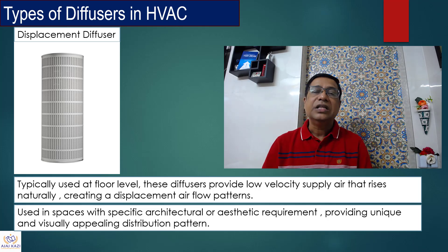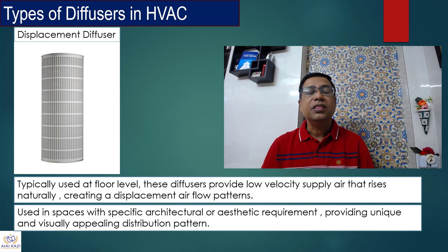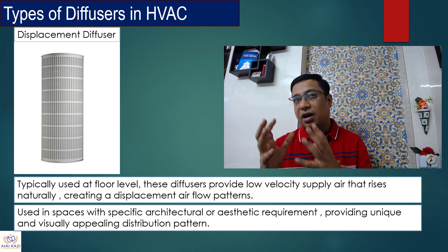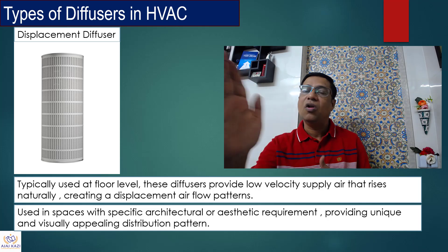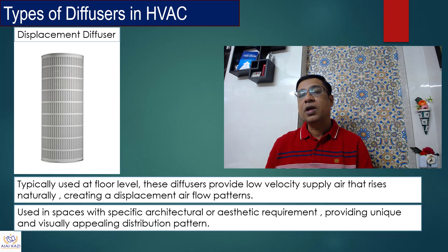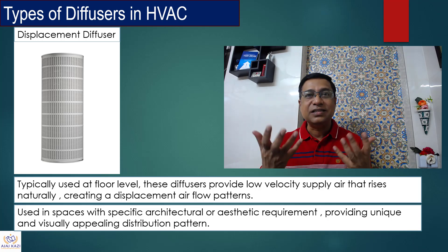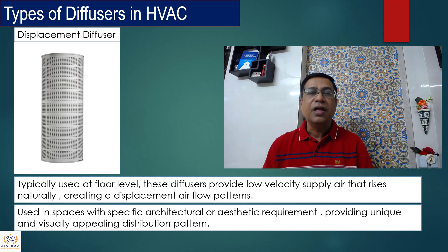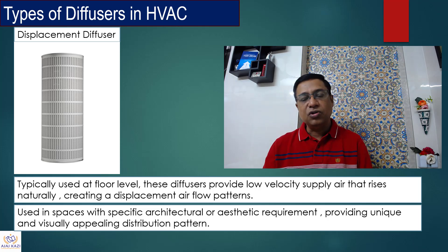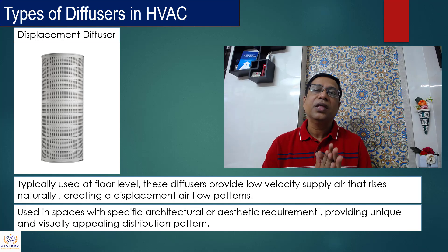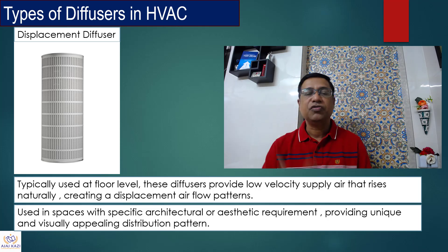This is called a displacement diffuser, and it is not that commonly used. Generally you must have seen these in airports, lobbies, or arrival and departure lounges. These are at floor level and are generally low velocity supply air risers, so you don't get a draught when you walk near these diffusers. If you put a diffuser on the floor and walk nearby, you would normally find a draft of air which is generally irritating. So these are low velocity floor type diffusers — the air rises from below and gets diffused to the area to be conditioned. This is basically an aesthetic requirement from architects, and you must have seen these in airports or large spaces where air distribution is from the floor.